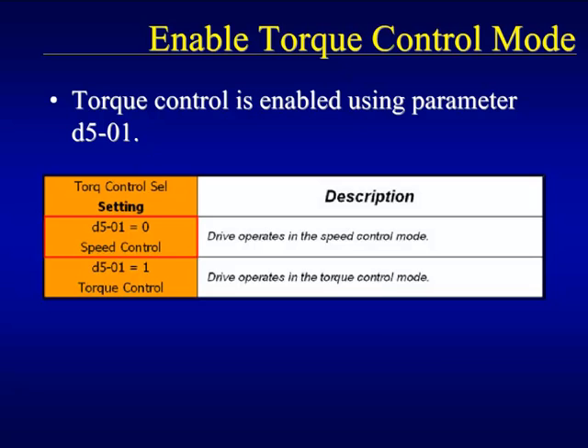The D5 parameter group contains the Torque Control mode parameters. The first parameter, D501, is used to enable the drive to run in either speed or Torque Control mode. Note that the red box around setting zero indicates that the parameter is factory set to this value. Enabling Torque Control is accomplished by setting D501 to setting one.